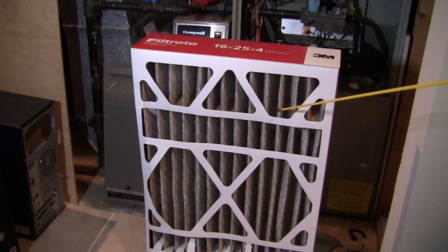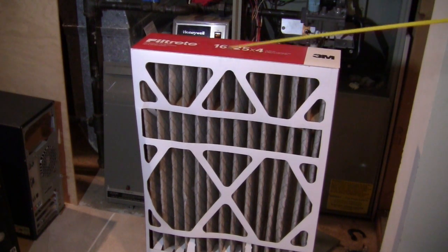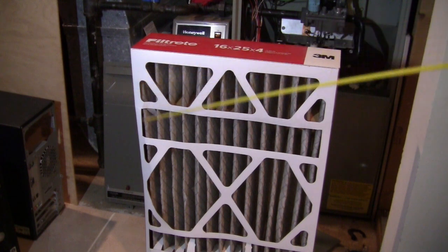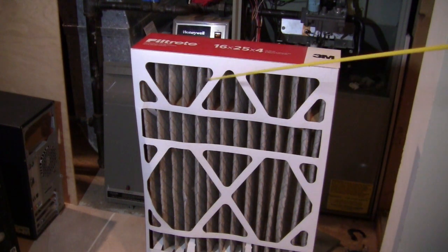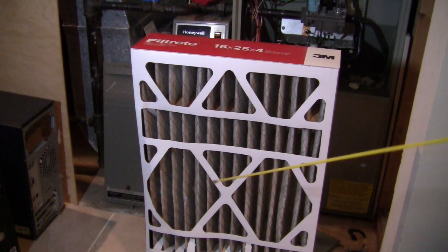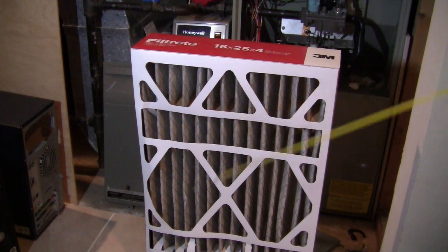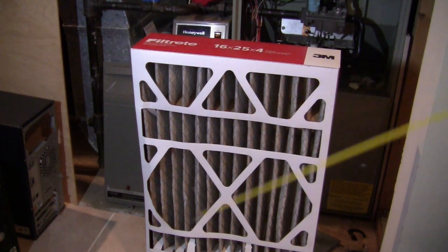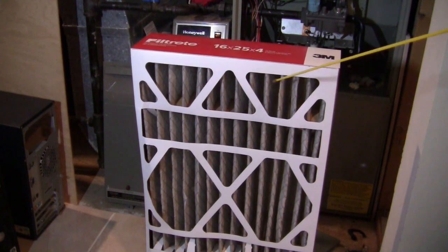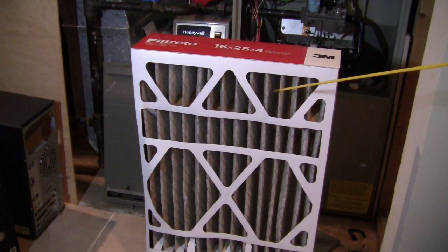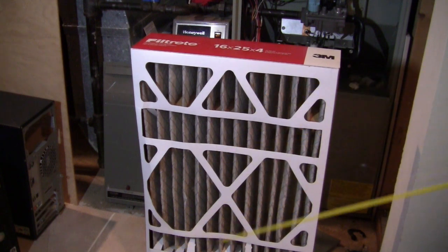What does this mean? It means if you don't change this filter for a long time, all of this gets broken, and the vacuum power from the fan will suck this material into the fan. But because this metal over here is connected to the container, it blocks this material. Anything broken can't fly into the fan or fly into the outlet.